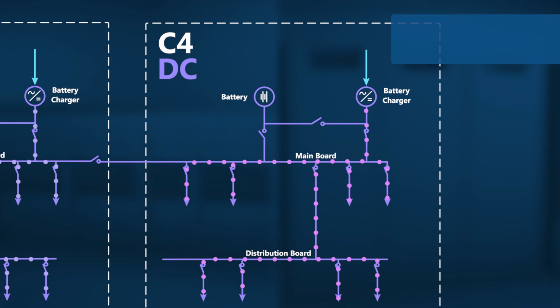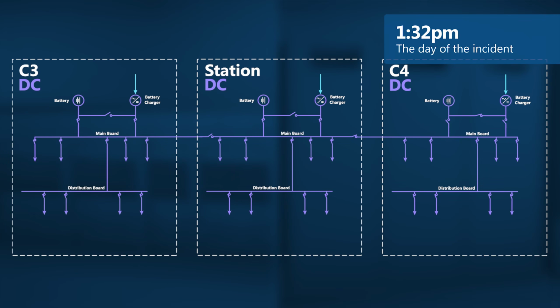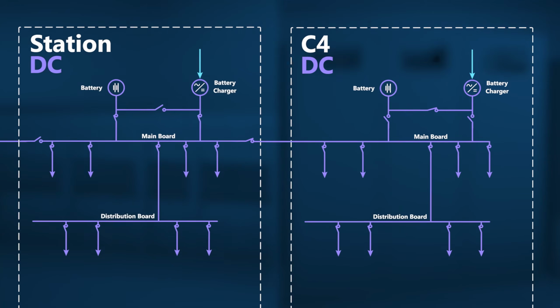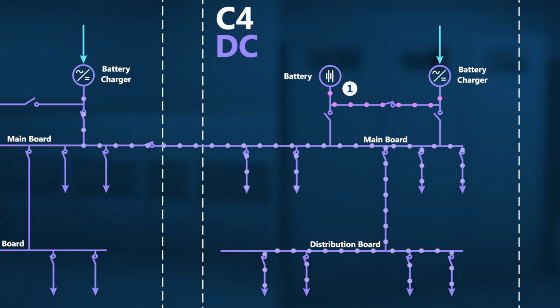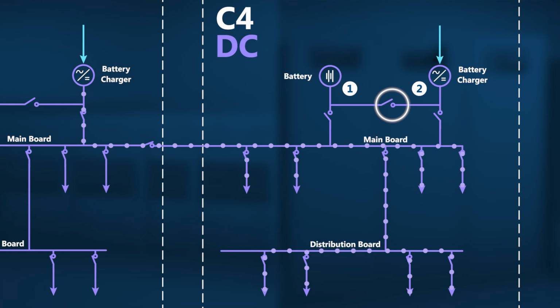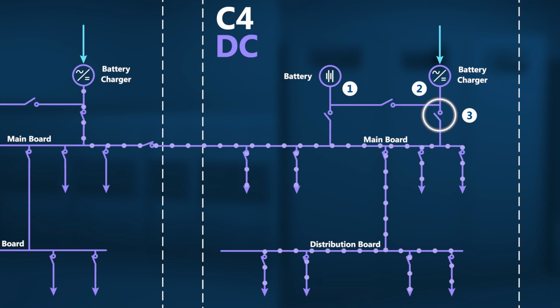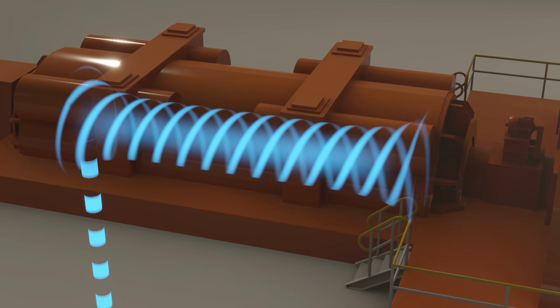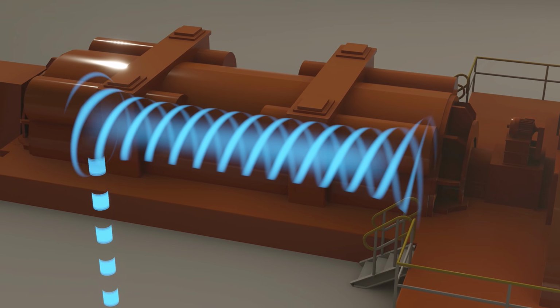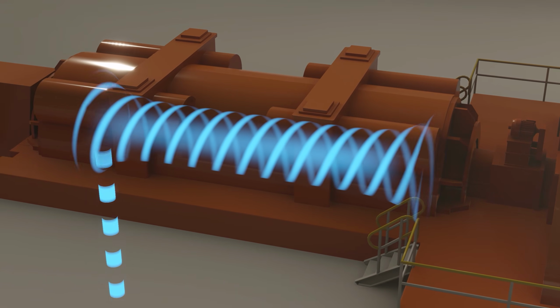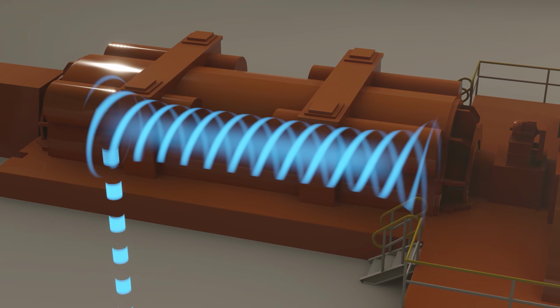By 1:32 p.m. on the day of the incident, the first 3 steps of the switching sequence had been carried out successfully. The battery had been fully charged, the battery charger had been disconnected from the battery. It had then been connected to the DC system. At this point in time, the turbine generator was still spinning at 3000 RPM and exporting power to the grid. Then, as the 4th step was completed and the interconnector was opened, all of this changed.